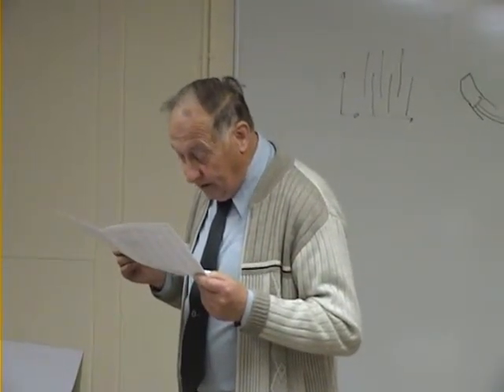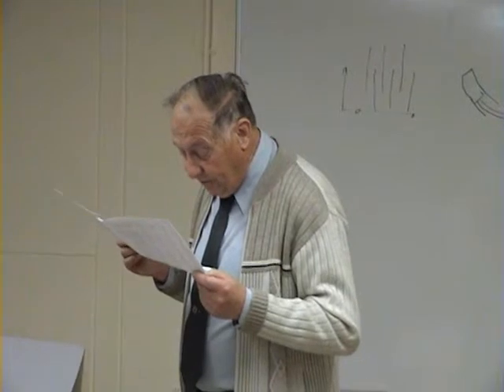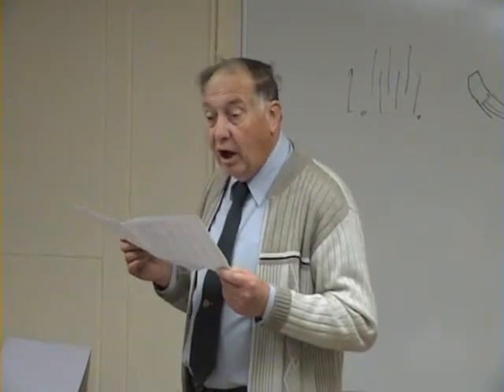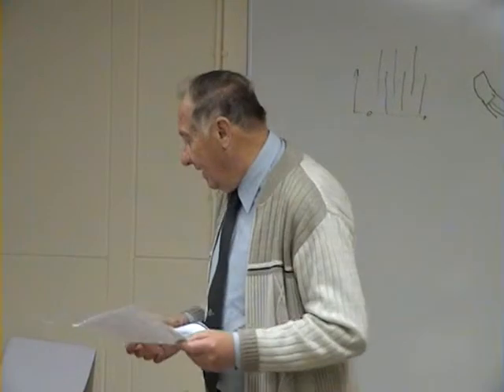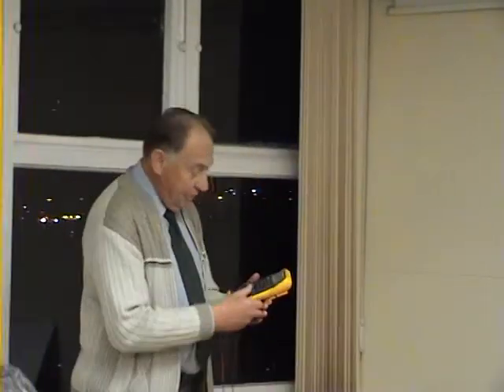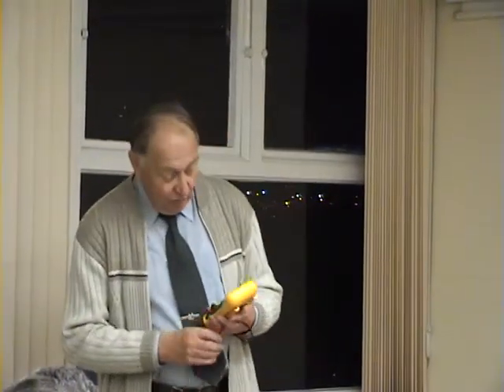There's another one here, 0.37%, plus 100 counts. What that's telling you is that when you go and put this meter onto a circuit, it says that it's reading 10.00 volts. Actually, I'm maligning Fluke, it was very good. But one of the other ones reads 10.00 volts, but it also could read 10.1000. It was a plus 100 counts.